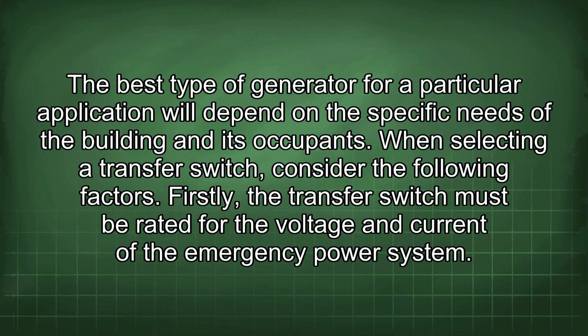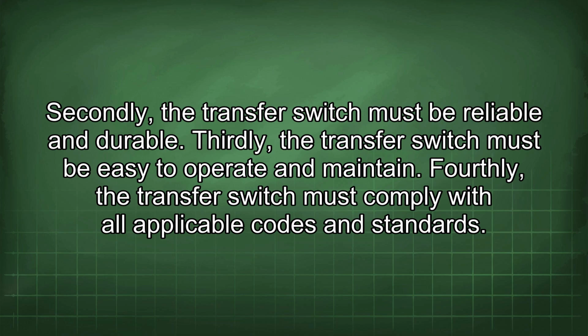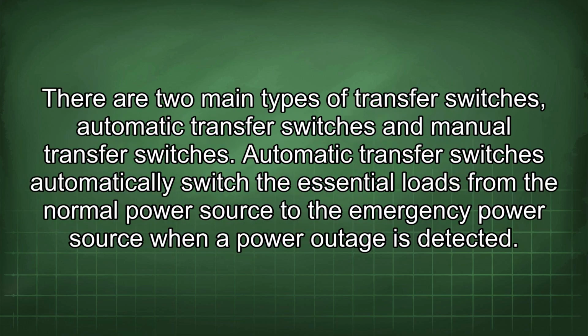When selecting a transfer switch, consider the following factors. Firstly, a transfer switch must be rated for the voltage and current of the emergency power system. Secondly, the transfer switch must be reliable and durable. Thirdly, the transfer switch must be easy to operate and maintain. Fourthly, the transfer switch must comply with all applicable codes and standards. There are two main types of transfer switches: automatic transfer switches and manual transfer switches. Automatic transfer switches automatically switch the essential loads from the normal power source to the emergency power source when a power outage is detected.